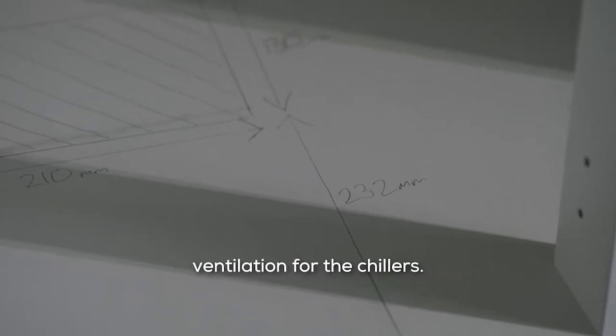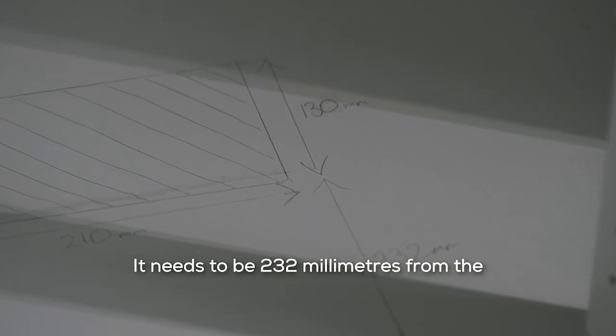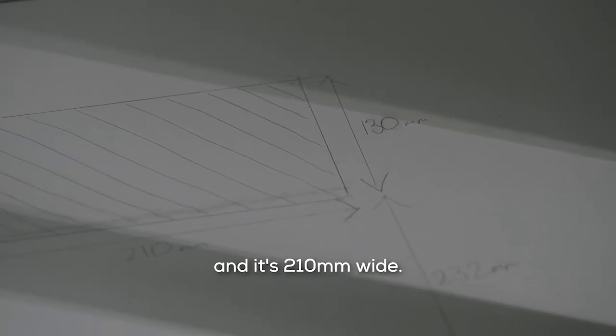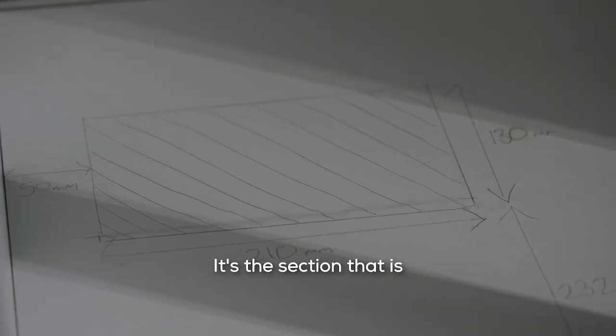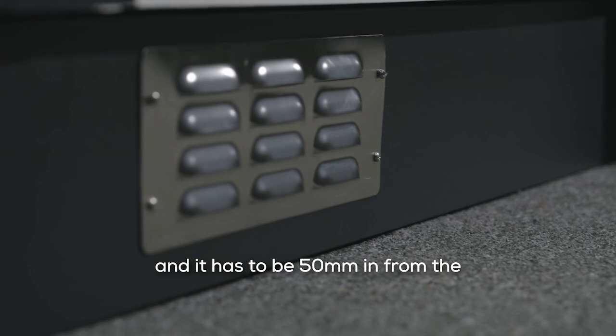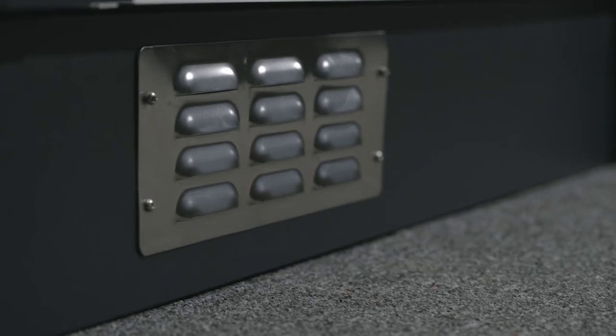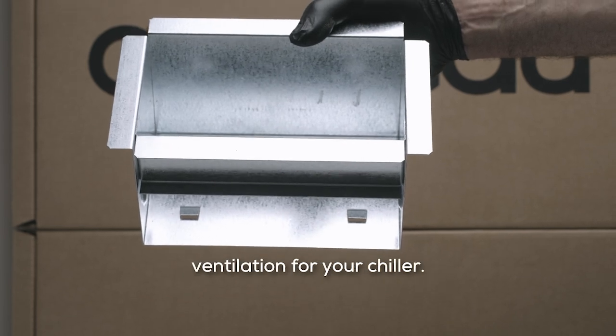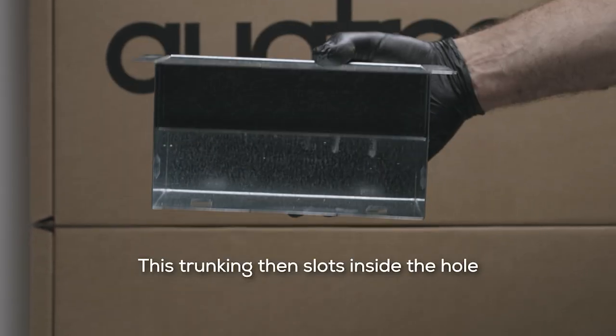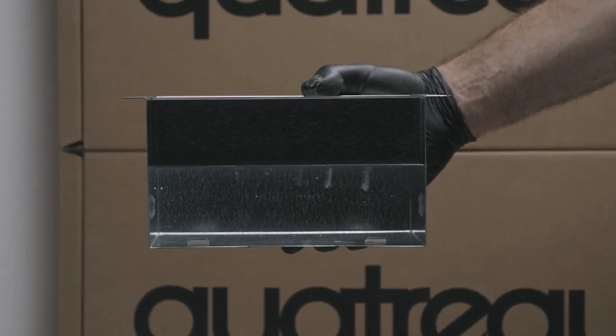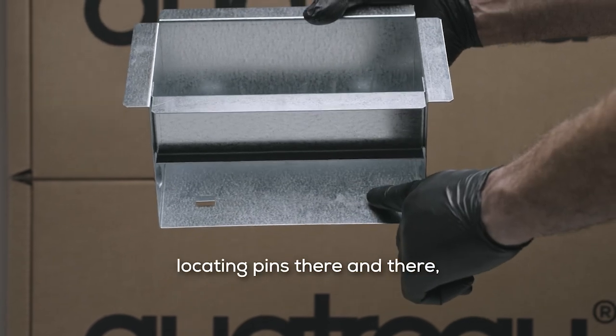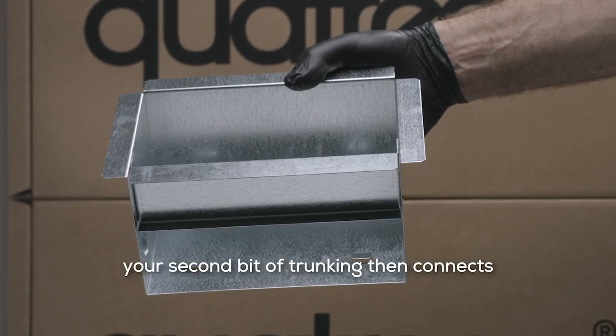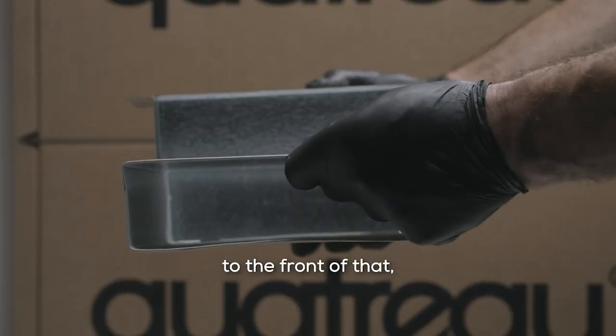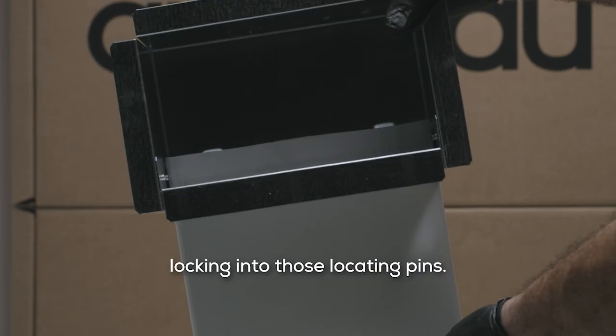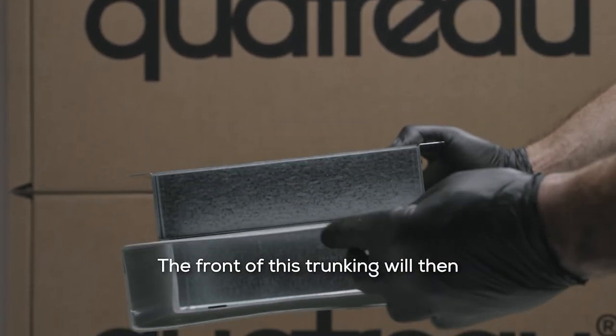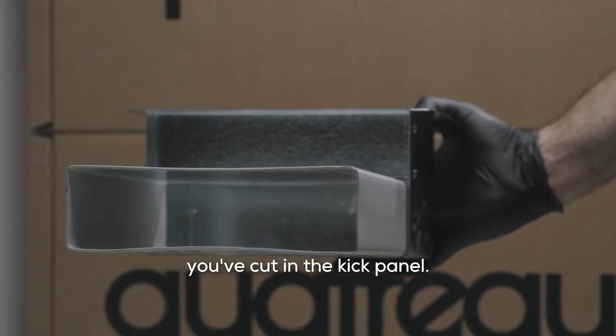This is option 2 for the essential ventilation for the chillers. It needs to be 232 millimeters from the front of the cupboard, and it's 210 mil wide. It's the section that is shadowed out in this picture now, and it has to be 50 mil in from the left-hand side of the cupboard. This is the first part of your trunking for the ventilation for your chiller. This trunking then slots inside the hole in the kitchen cupboard. And if you see, there's 2 locating pins there and there. Your second bit of trunking then connects to the front of that, locking into those locating pins. The front of this trunking will then match up to the hole you've cut in the kick panel.